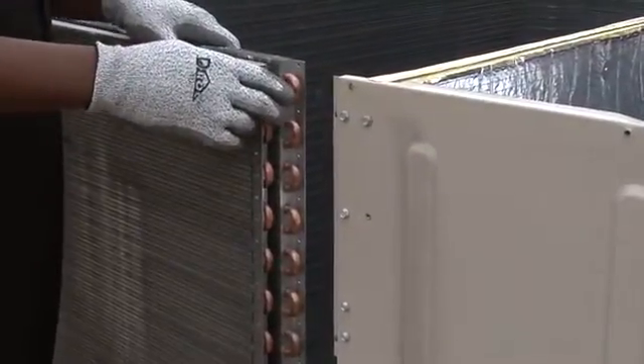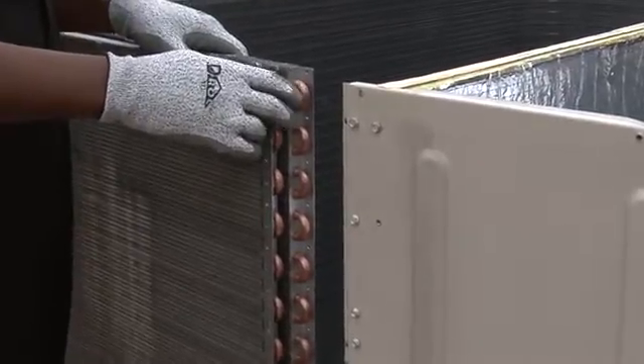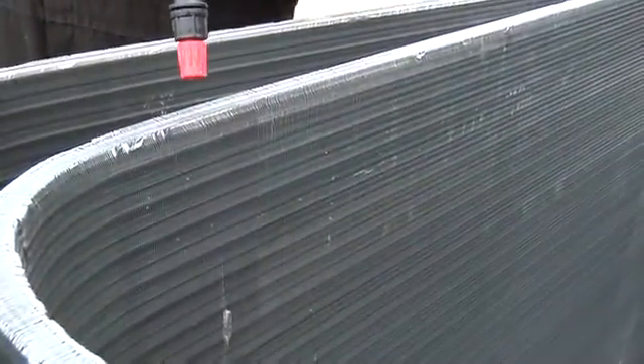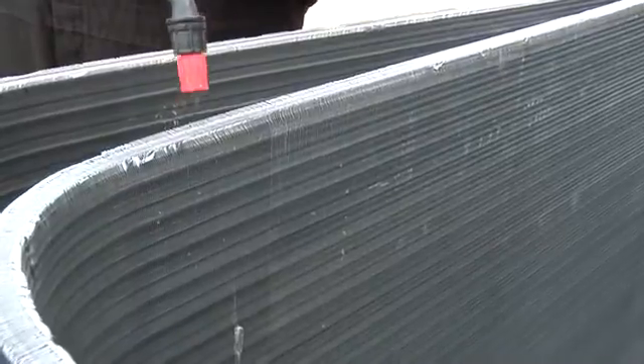Now you can see where I'm having to split the condenser coil for the two-row tube fin coil. That's how you properly clean a unit, which is time-consuming. You want to spray the condenser coils with degradable coil cleaner, spraying the coils on both sides, allowing the coils to soak for five minutes.